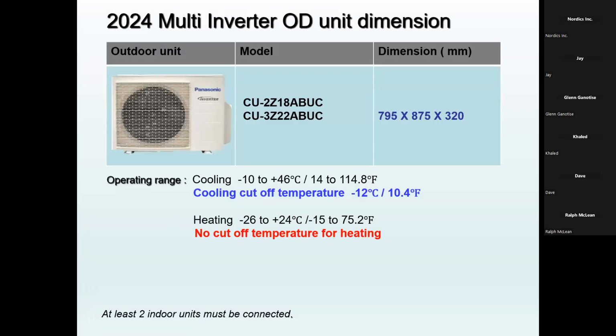As you can see here, what I just mentioned about the operation, we are good down to minus 26. There will be no cutoff like before. And in cooling, they will be cut off at minus 12. The older models would work down to minus 10. The new ones will work down to minus 12. Having said that, please do not install them in a computer room. If you want to run them down to minus 10 in a regular room just for regular cooling, that's okay. But we don't have units designed for computer rooms.